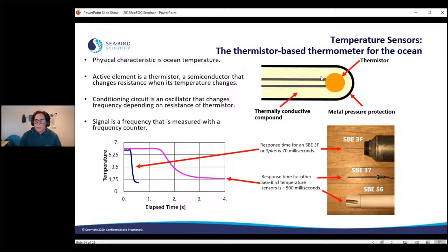One of the things I find amazing about this design is that these look like a simple metal tube, but they're not. They're actually designed so that when they get squeezed going down to pressure, it's not actually squeezing the thermistor—so the thermistor isn't sensitive to pressure changes. That tiny pin, about the size of a needle, has a thermistor inside it, and you can take that to full ocean depth, 10,000 meters, and it will get squeezed but not change.